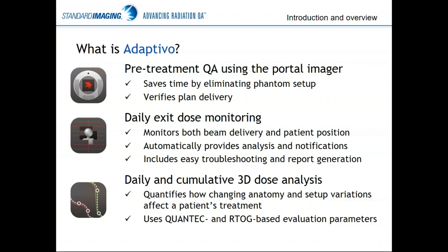The second thing we do with Adaptivo is daily exit dose monitoring — capturing the beam that's being attenuated by the patient. This is the real treatment beam during treatment, to monitor both beam delivery and some information about patient positioning. We analyze all the data automatically and notify you if there are things out of your set tolerances, and we include easy troubleshooting and report generation tools as well.